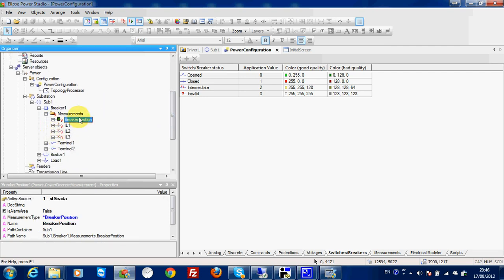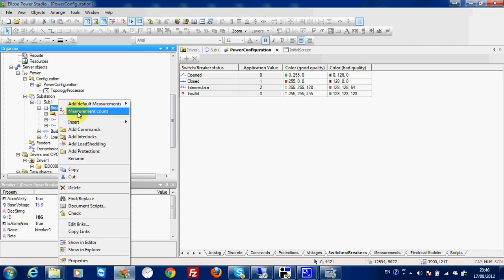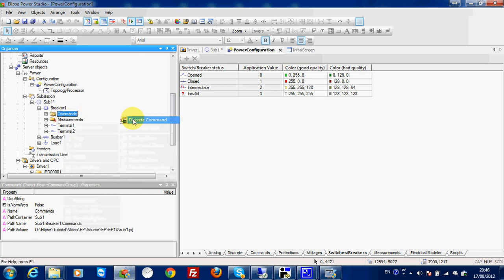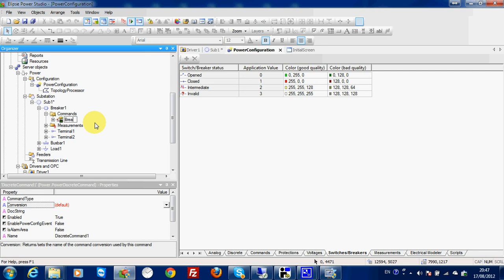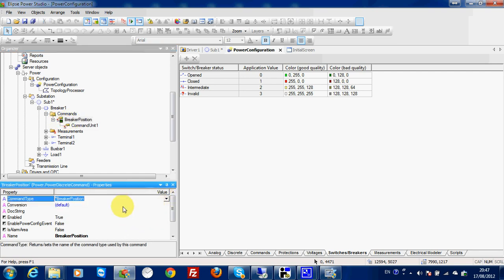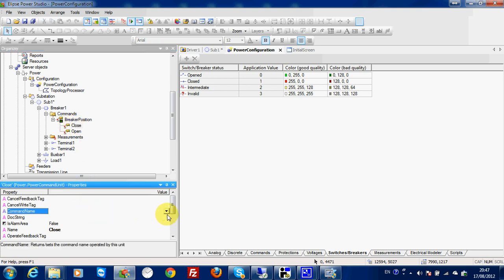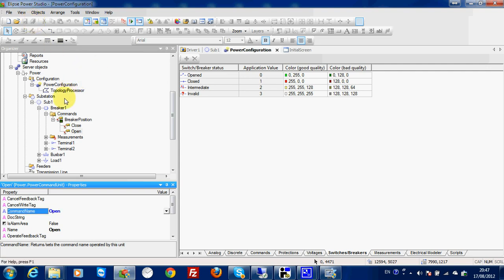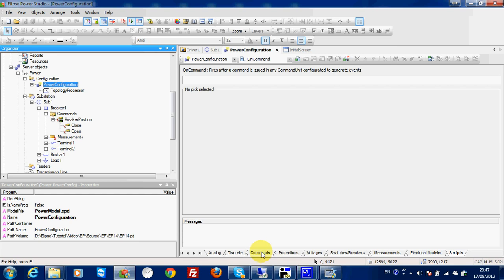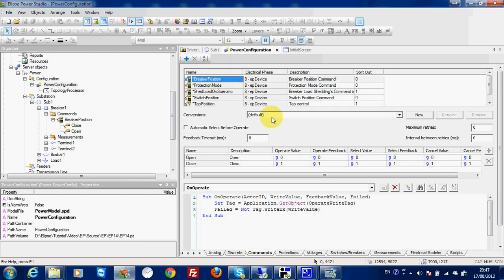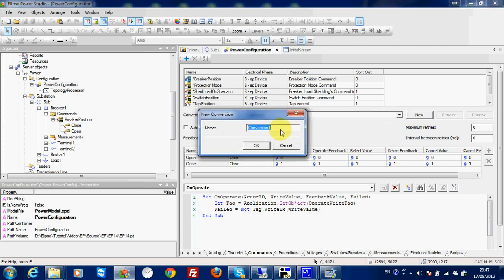Now I want to send a command. To send a command, I need to go to breaker one and add a command. Inside my command, I will insert a new discrete command that I will call 'breaker position'. This breaker position will be a breaker position. Then I also need to apply a conversion here. But before, I will prepare my two command units — one for open and the second for close.